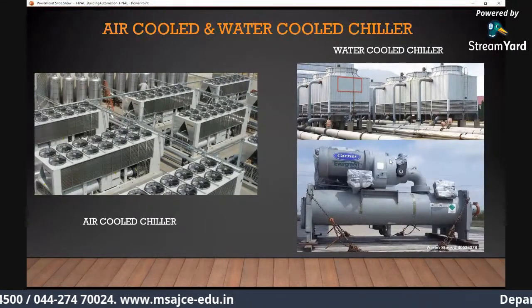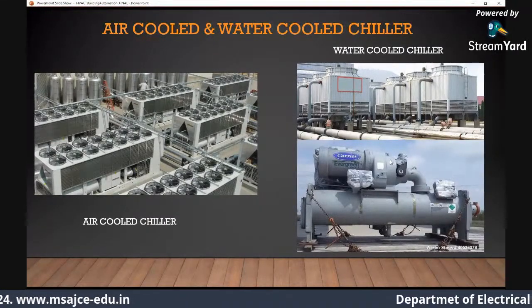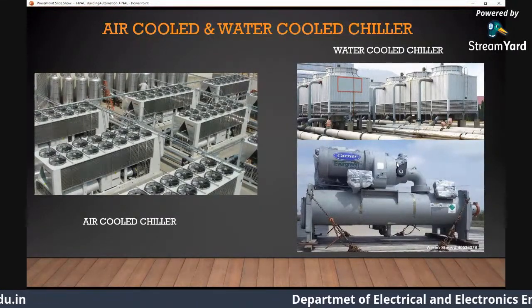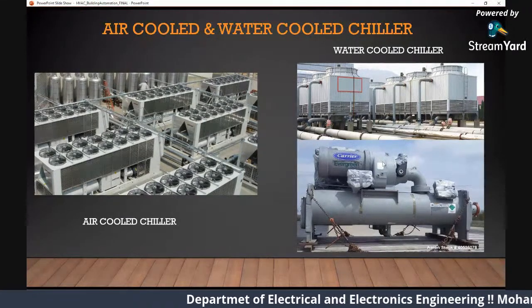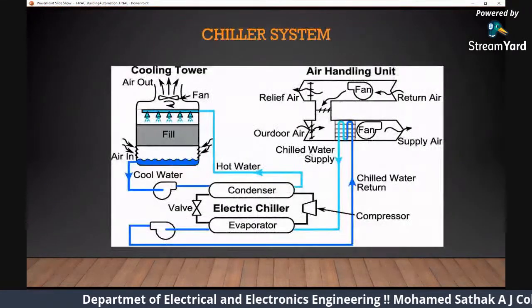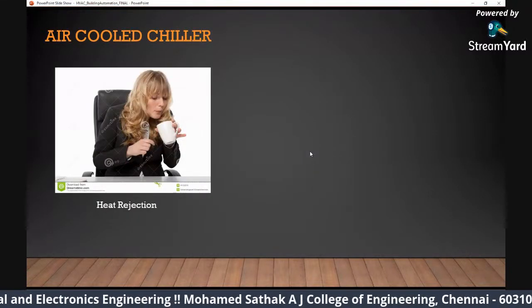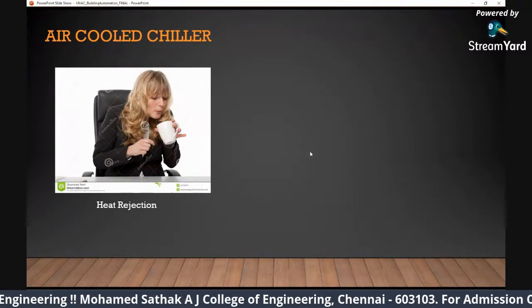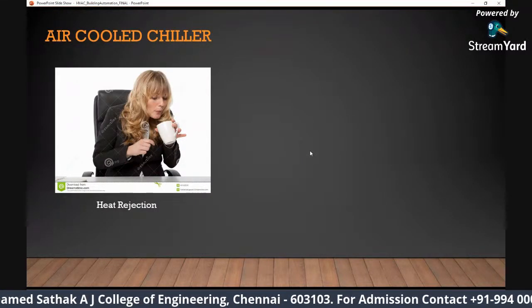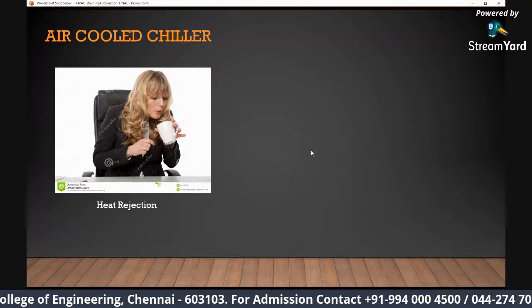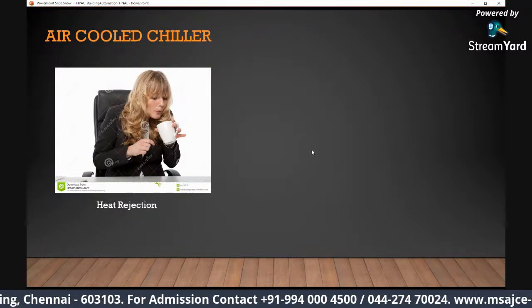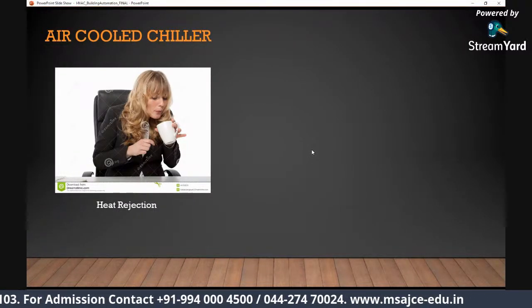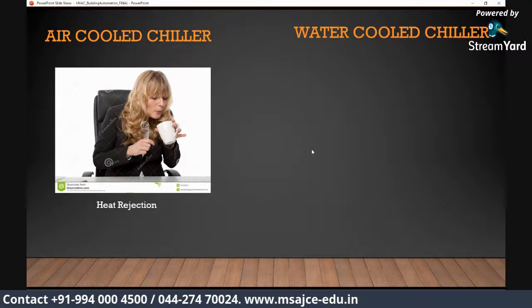So the water goes to the top of the cooling tower. There is a fan above. The water gets sprayed, and the fan. Let me show you a picture. Probably you'll understand. So this is your air cooled chiller. You have a refrigerant in your cup. Say it's a condenser. If you blow air, there's a fan above the condenser. It keeps on blowing air. It gets cool. So that's your heat rejection concept for your air cooled chiller.